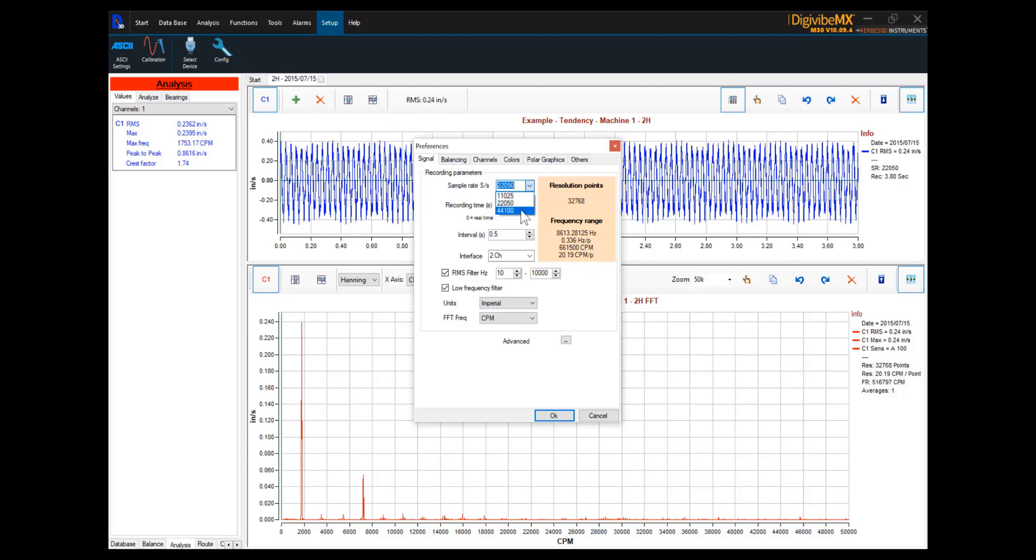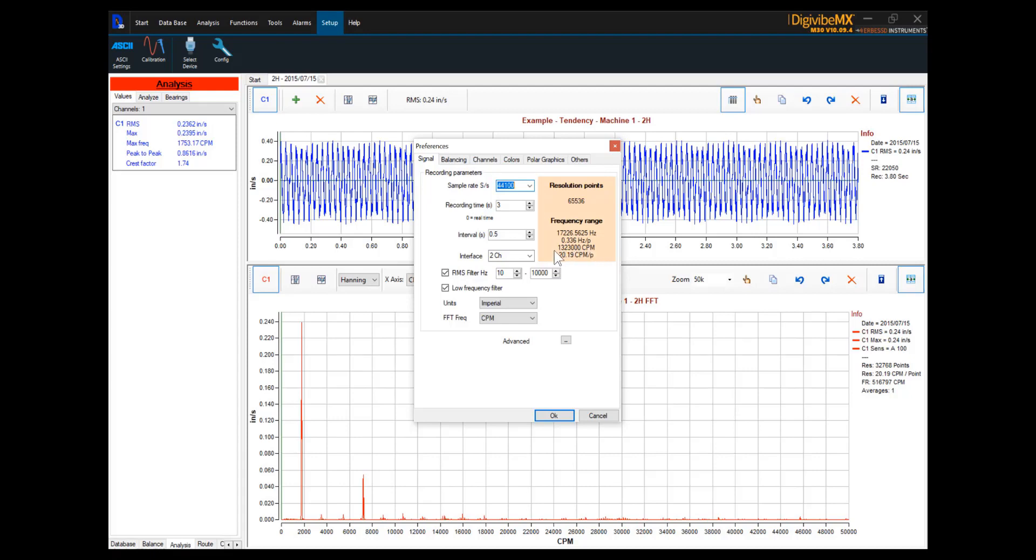On the highest setting of sample rate, 44,100 samples per second, our frequency range now increases to 17,226.5625 hertz, or 1,323,000 cycles per minute. And that would be the maximum frequency range detectable on this FFT collection at 3 seconds.